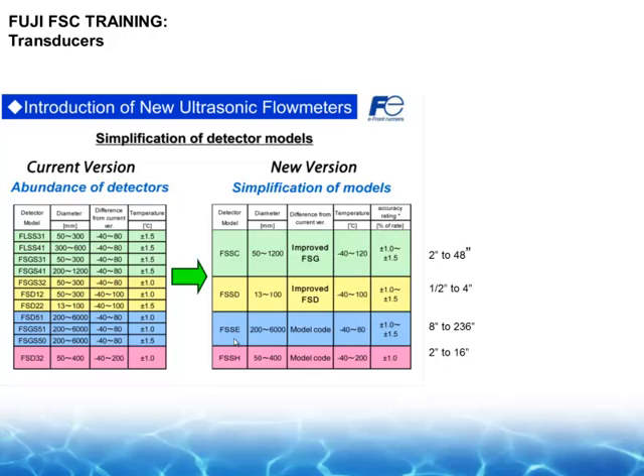It does have, little known, a half megahertz sensors, which are both about the size of a brick, that you would use more so for like your penstock applications, your 100-inch pipe applications. So they're not designed, I wouldn't recommend to use them for your 8-inch applications. Definitely use this device there. As I said, though it's rated for 48, I'm sure you can probably get up to 60. So when you get above that, then consider this application there. And they also have an extremely expensive high temperature sensor there, which works for pipe sizes 2 to 16 inches. We do have some other choices if you get into that kind of problem.